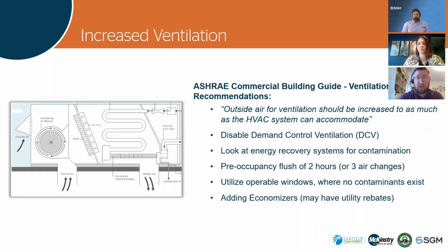This is going to clean the air, but also, if you're using an increased amount of chemicals, this is going to be a good way to keep people's respiratory systems healthier. Lastly, if you have operable windows with no contaminant sources, use them. And it's a good time to consider adding economizers to your systems if you have older fixed outside air dampers.